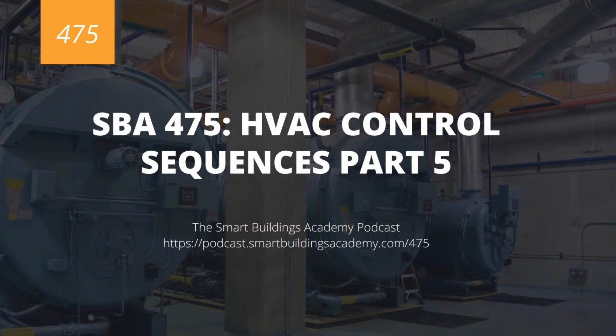And finally, you have lead lag control, right? So this is very similar to lead lag control with the pumps, except we're doing this with the boilers. Now, if we fail to meet set point in a purely lead lag scenario, nothing's going to happen. So I want to be very clear on that, and a lot of folks will get kind of thrown off by this. There is another version of lead lag, which is peak load conditioning. Basically what happens with peak load conditioning is we look at, am I not meeting set point? And if I'm not meeting set point, the lag device can either match the control conditions of the lead device.